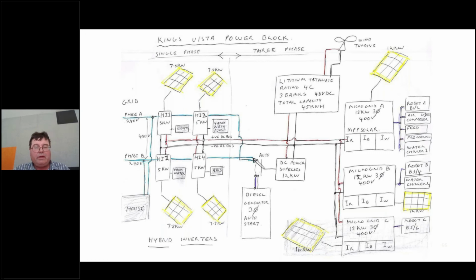I could have made the 3 microgrids as one big microgrid, but just to add more reliability and redundancy to the system, it's all plug and play. So should one microgrid go down for some reason, my only worker I have at home knows that he can ring up and he'll just swap plugs over to run it all on microgrid B, for example. Microgrid C is greyed out. It doesn't show it being greyed out here, but it was greyed out. It's what will come with the 16 kilowatts going on the western wall. So pretty much redundancy, backup, full system.